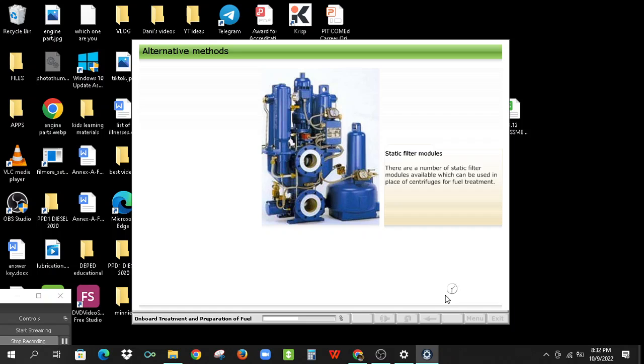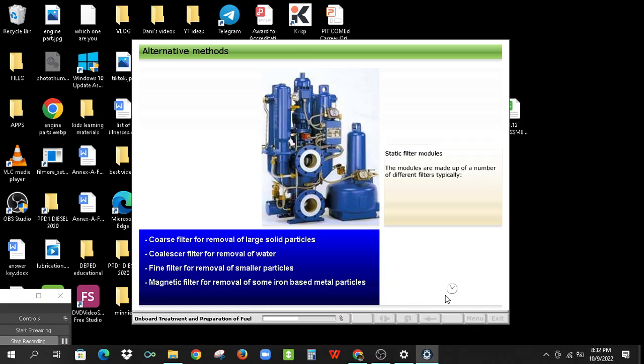There are a number of static filter modules available which can be used in place of centrifuges for fuel treatment. The modules are made up of a number of different filters, typically coarse filter for removal of large solid particles, coalescer filter for removal of water, fine filter for removal of smaller particles, and magnetic filter for removal of some iron-based metal particles. These units are more common for service in either distillate fuel systems or lubricating oil systems. It is unlikely that you will find them used with heavy fuel systems unless there are centrifuges also fitted.